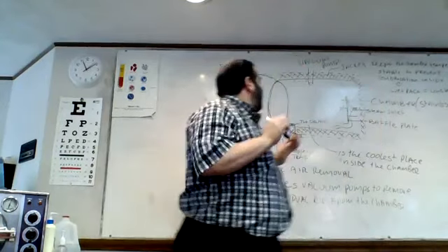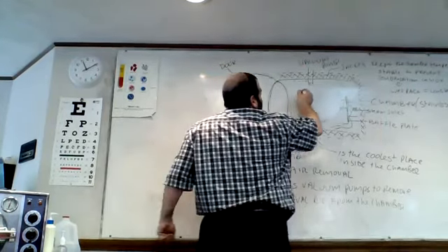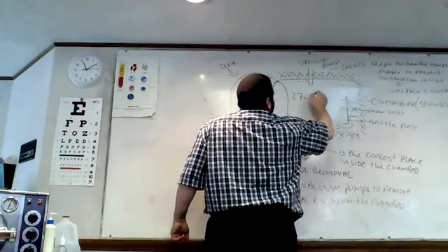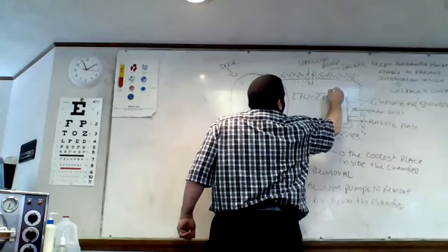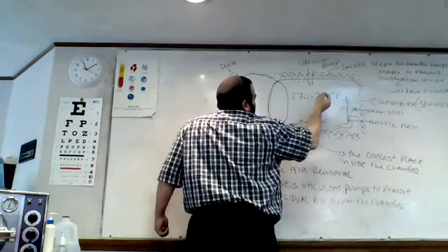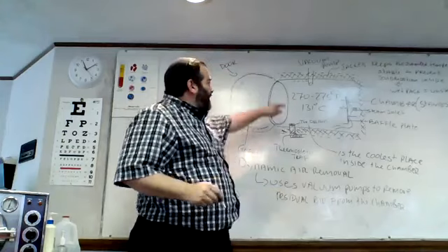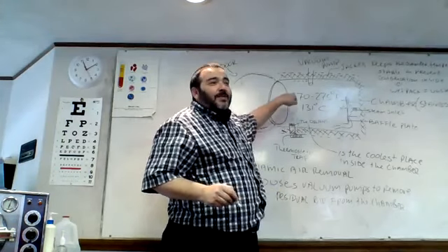By the way, I did mention to you that the dynamic air displacement system runs between 270 and 275 degrees Fahrenheit, which is roughly 131 degrees Celsius. That's the dynamic air displacement temperature.